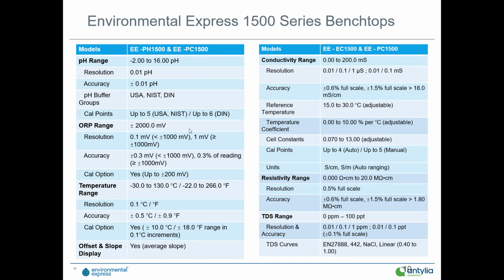Full ORP range, good accuracy, good repeatability, the temperature range, -22. That'd be interesting to measure because most solutions will be frozen at that point, but all the way up to 266 Fahrenheit. Key option here is that the temperature can be calibrated and adjusted if the temperature element has drifted at all. Offset and slope display, which is key for indicating the health of the electrode. I'll talk a little bit more about that down the road here, but that's a key thing you can quickly check.